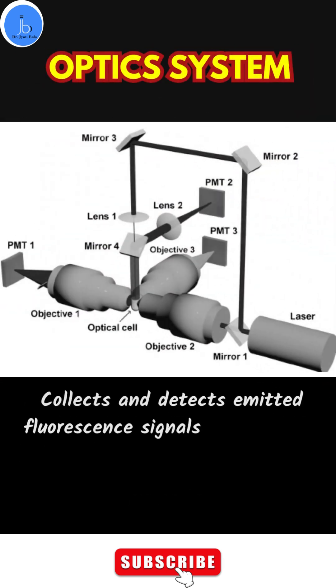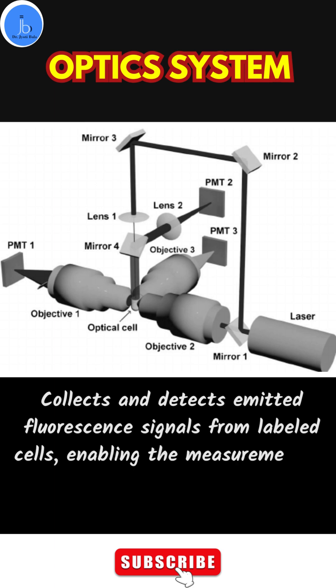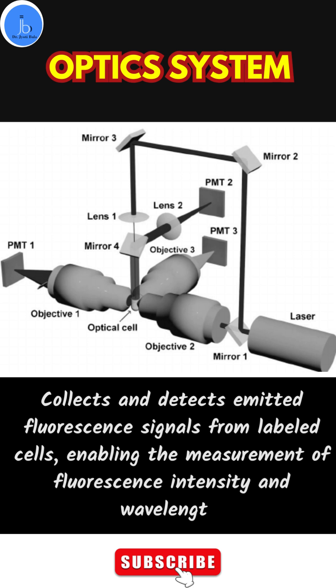The third one is the optic system, which collects and detects emitted fluorescence signals from the labelled cells, enabling the measurement of fluorescence intensity and wavelength.